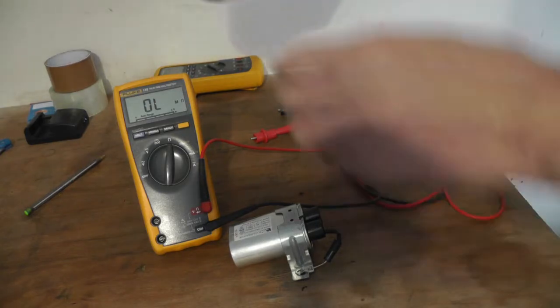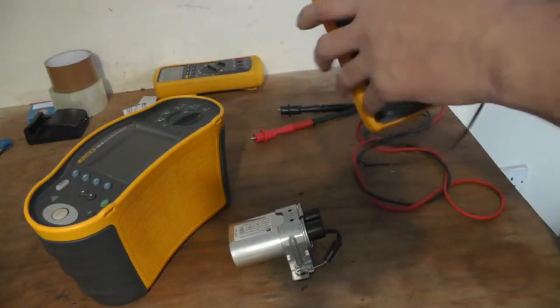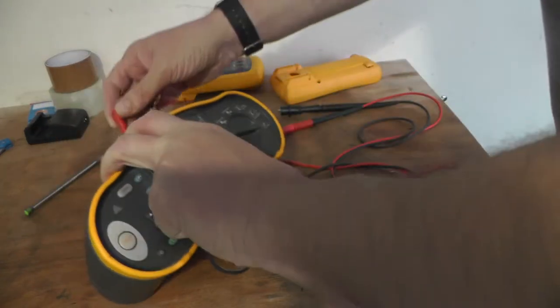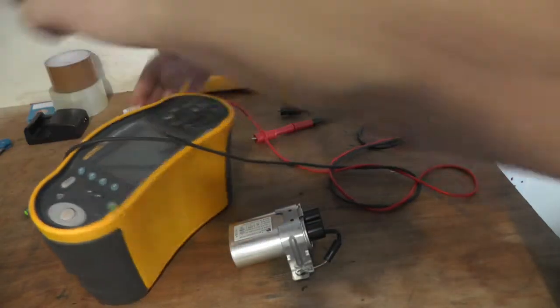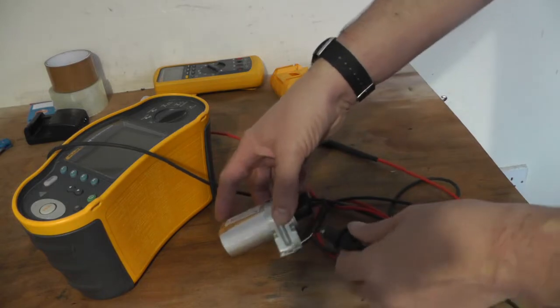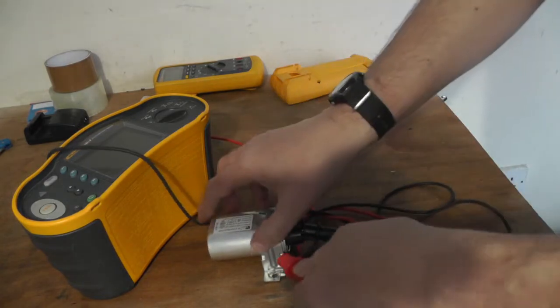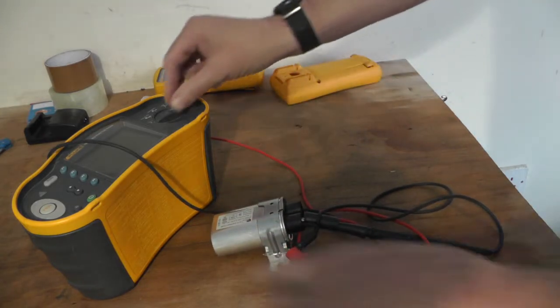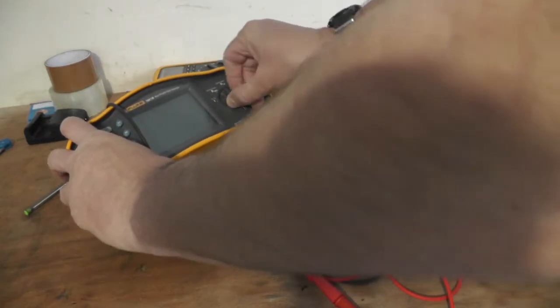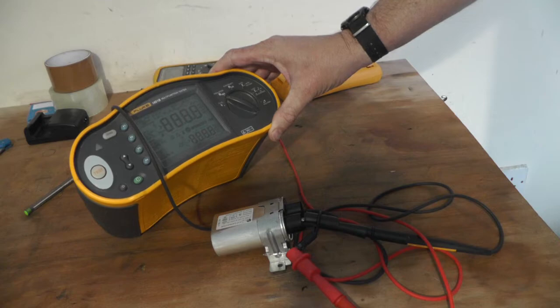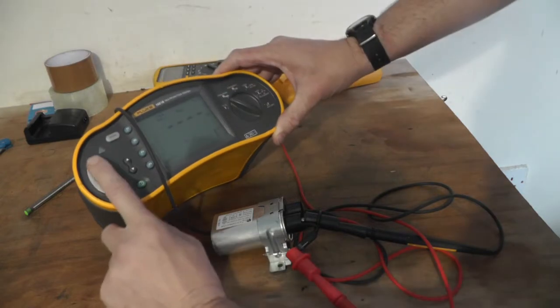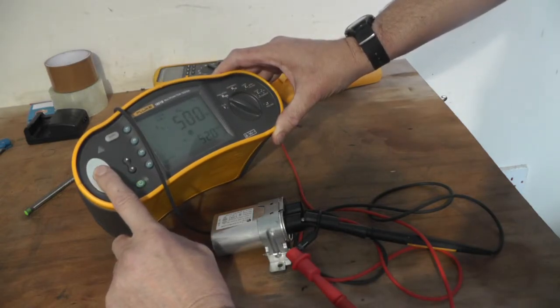In fact, I'll just try my insulation resistance tester to see if that will pass electric through at 500 volts. I'll do it at the negative side, this side first. It shouldn't read. I'll just move it away from that body. So I've got it at 500 volts. So greater than 500 megaohms, so it's not passing any current that way.